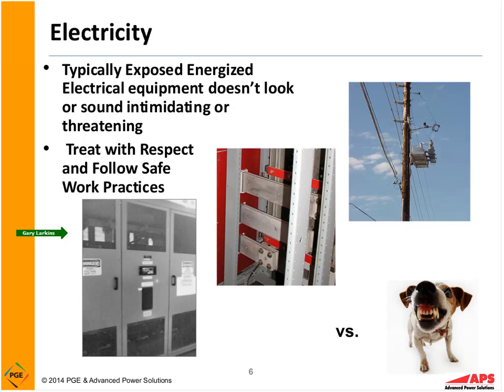And the risk of a hazard is much lower when the doors are all closed. But that doesn't mean that there is no hazard whatsoever. We've had several cases where, whether it be contamination, a damaged part, or a rodent getting into electrical gear, we've had explosions take place. And as you can see from all the vent holes on the top and bottom of this equipment, that gear is not going to contain the arc flash incident energy level.